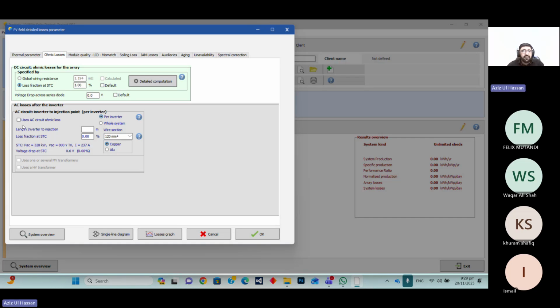So as per my experience, they don't allow us higher than 1 to 1.5%. In between, they will restrict the contractor, saying they will not accept a voltage loss higher than this. So we have to increase our cable sizing to save the systems from this loss, and we have to oversize our cables.